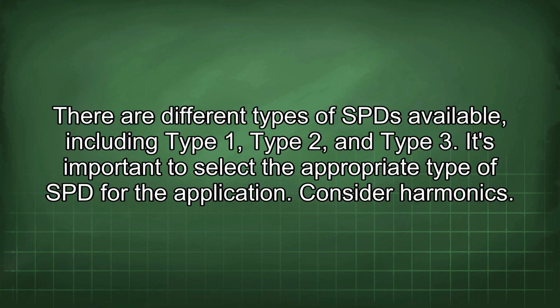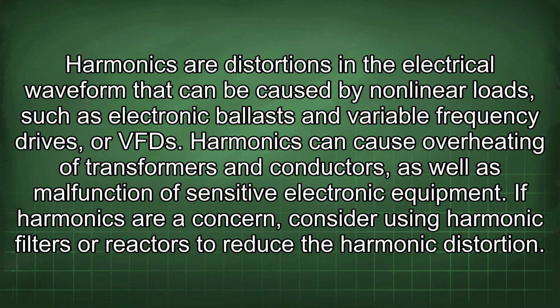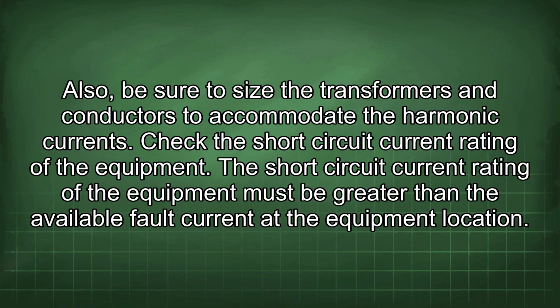Consider harmonics. Harmonics are distortions in the electrical waveform that can be caused by nonlinear loads such as electronic ballasts and variable frequency drives, or VFDs. Harmonics can cause overheating of transformers and conductors, as well as malfunction of sensitive electronic equipment. If harmonics are a concern, consider using harmonic filters or reactors to reduce the harmonic distortion. Also, be sure to size the transformers and conductors to accommodate the harmonic current.